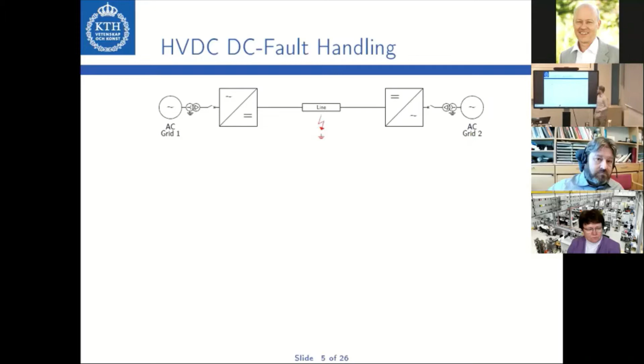Conventionally, one would handle this kind of DC fault by opening the AC circuit breakers of the converters. In this case, the DC fault is isolated from the AC side. This is a rather slow process. Another possibility that has been used is to use the converters to actually control the fault current on the DC side throughout the fault. The thing is that this requires converters that still have control under a DC fault. The converter that is expected to be used in HVDC grids, however, does not have this capability. Another option are DC circuit breakers, which are now included on the DC line. DC circuit breakers are typically not used because they are quite complicated and expensive.